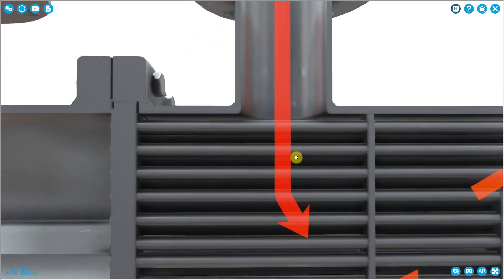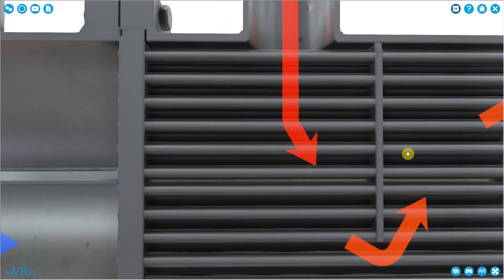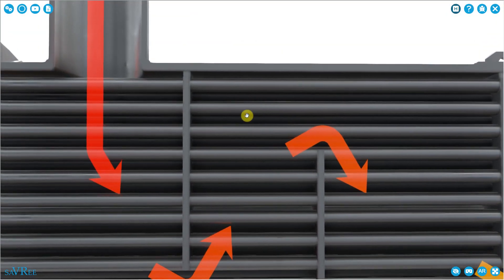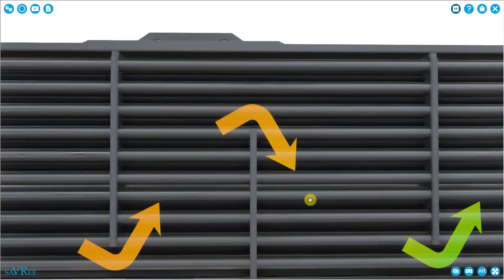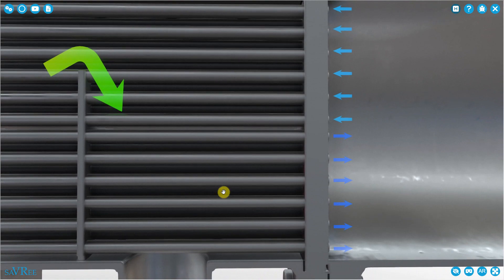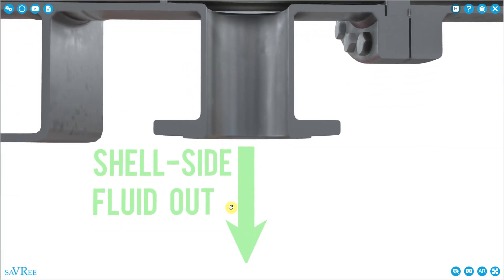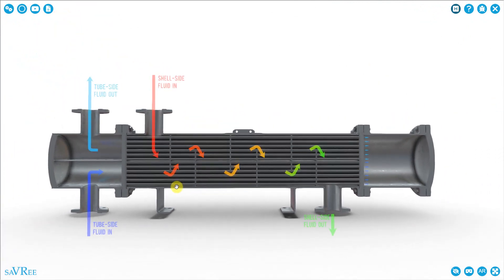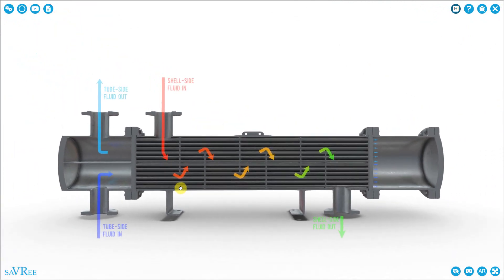We've got a shell side fluid, and you can imagine that it flows on the shell side. It comes in here and it's going to surround the tubes. Then it's forced around these baffles, and in this way we can transfer a lot of heat before the fluid is discharged through this connection here and out the bottom. So that's one type of heat exchanger — there are different designs and variations but they all come under the classification of a shell and tube type heat exchanger.